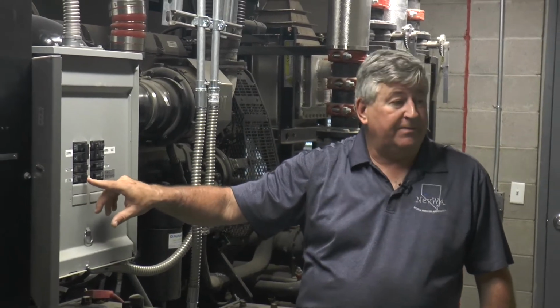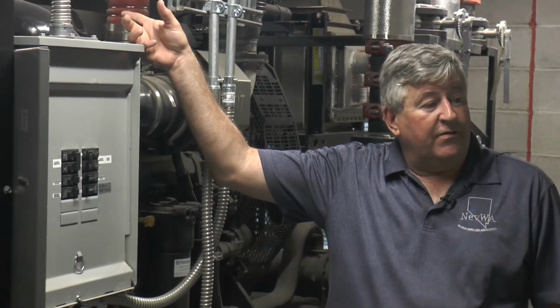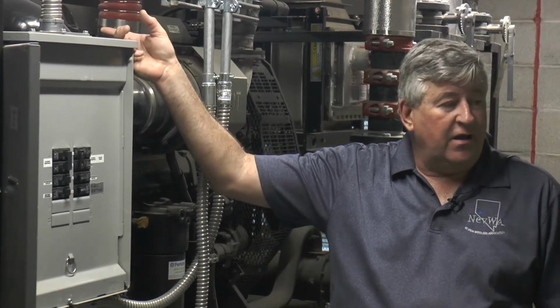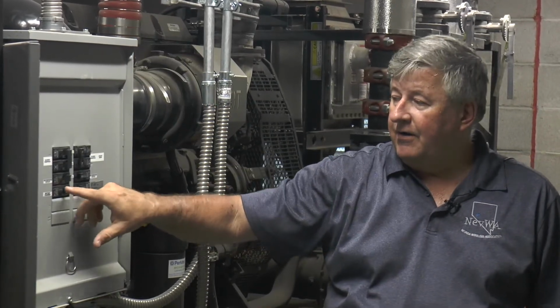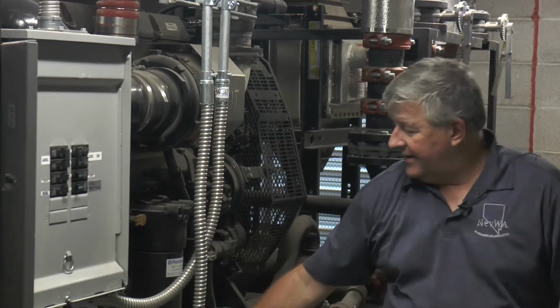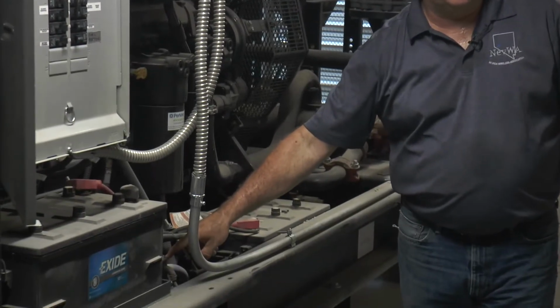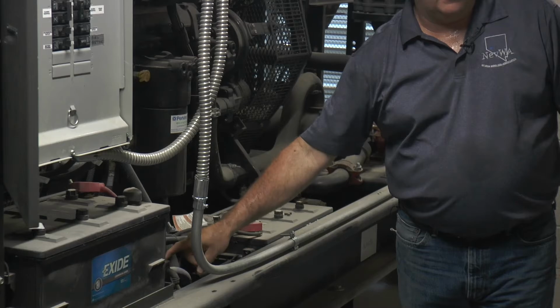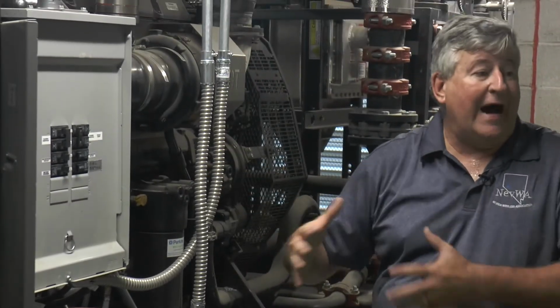So in the event that you have a failure with your battery charger, two things you've got to look at. One, is this breaker tripped, or is the breaker in the other room tripped? If the breaker in the other room tripped, you're probably going to have a low coolant temp alarm. That'll let you know that you lost power. You've got two of the same events happen at the same time.